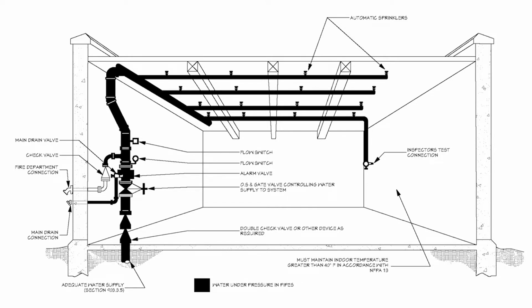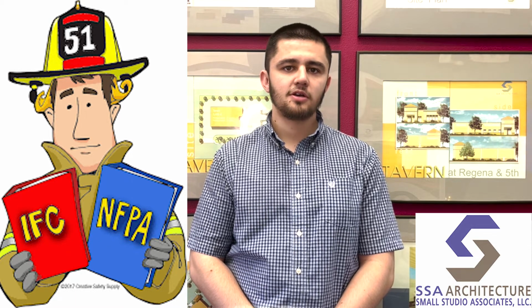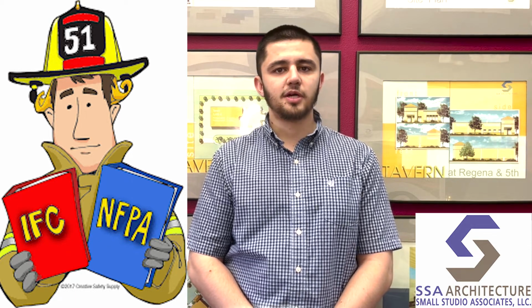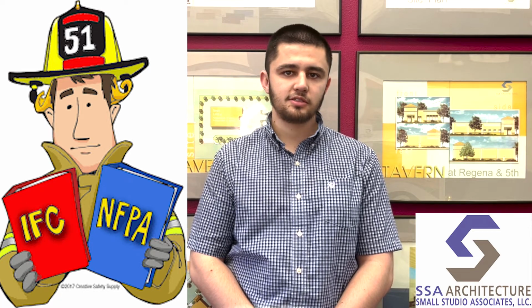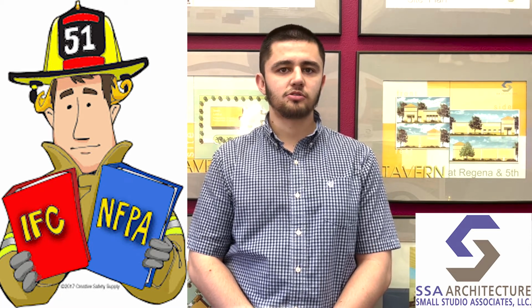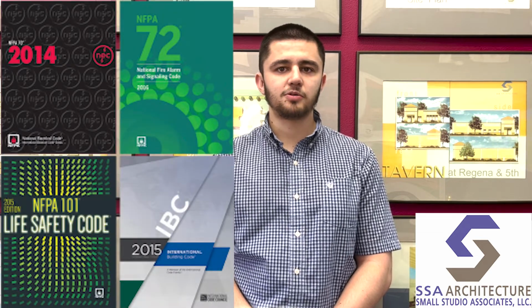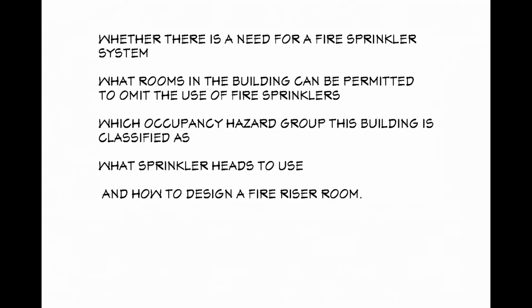These systems are regulated by the local authority in a process typically starting with a fire plan review and ending with the final fire inspection. While analyzing the proposed fire suppression system, these reviewers and inspectors usually base their evaluation on the International Fire Code, the NFPA 13 standard for installation of sprinkler systems, and other applicable fire code books. We will look into how the code requirements can help designers determine stuff like whether there is a need for a fire sprinkler system, what rooms in the building can be permitted to omit the use of fire sprinklers, which occupancy hazard group this building is classified as, what sprinkler heads to use, and how to design a fire riser room.